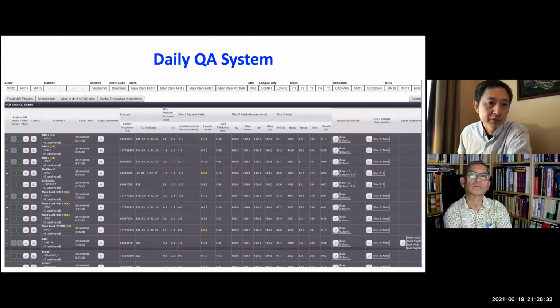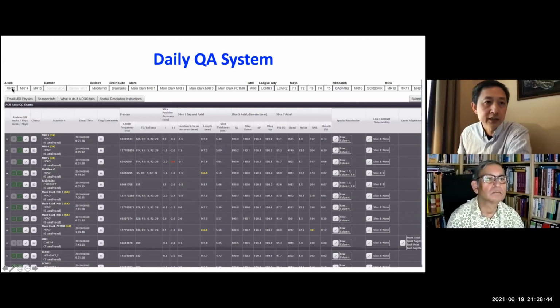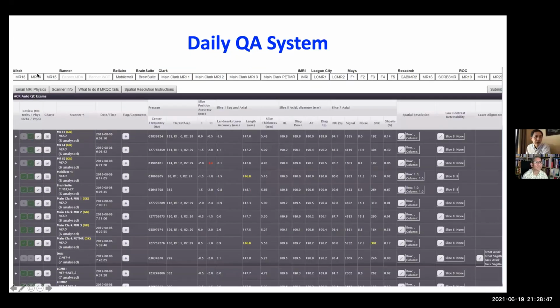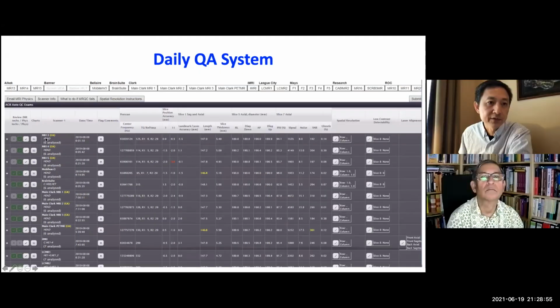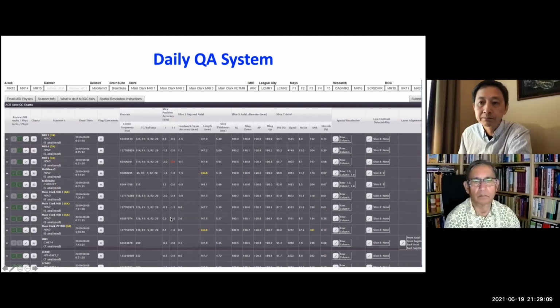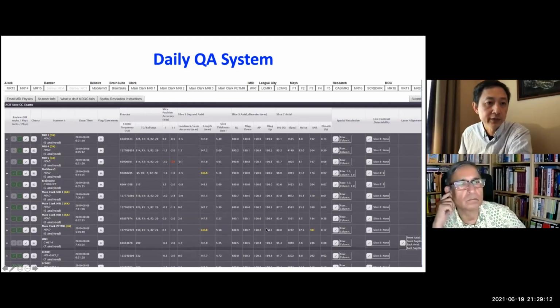This is an example of our daily QC system. I mentioned that for every scanner we do the ACR QC. On top, in a very small font, this lists the 30 scanners, so very quickly we can see which scanners are on and which are down. Each line is one scanner: MR13, MR14, MR15, and they show the results of the ACR measurement. Very quickly we see there's a red flag there, and a yellow flag on a particular scanner. So physicists monitor this every day.